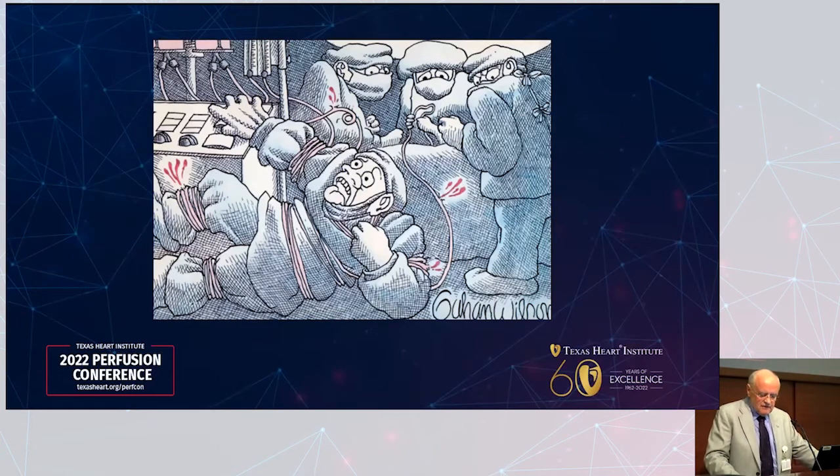For venous reservoirs, they initially used reservoir bags with membrane oxygenators for safety — similar to an IV bag, it closes when empty. Eventually the perfusion department moved toward hard-shelled reservoirs for simplicity. For cardiotomy reservoirs, they initially used non-filtered versions and attached external depth filters, foam filters, and screen filters below the reservoir for additional filtration. A few years later, manufacturers produced cardiotomy reservoirs with built-in filters inside.